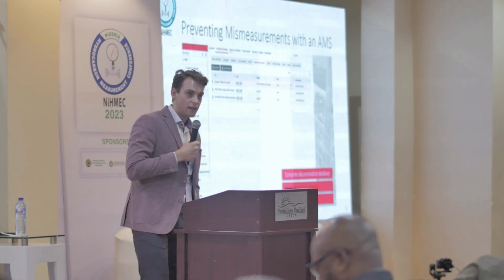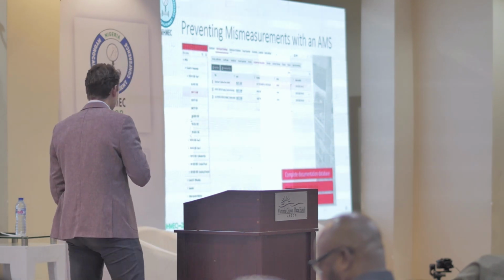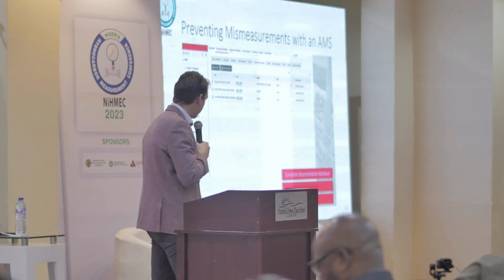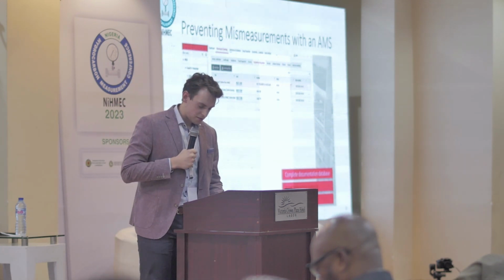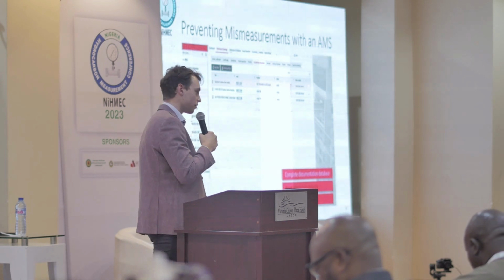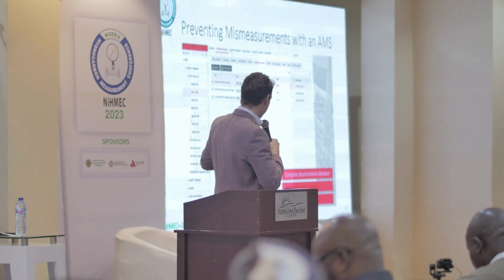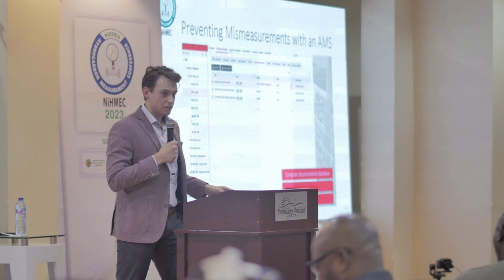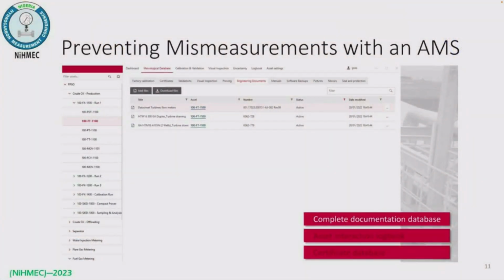So what could be one of the software tools you can use? First, by having an asset management system, you can get the documentation for each and every asset, for example for the meter or the transmitter, in a single, clear space. This makes it easy for an operator to find documents, drawings, and data sheets during initial troubleshooting, because you need to know under which conditions it was originally designed, and that needs to be readily available. We often still get questions from operators about documents that were delivered at the end of our projects, and we think, how could you not have, for example, a P&ID of a complete metering system if you are the operator?